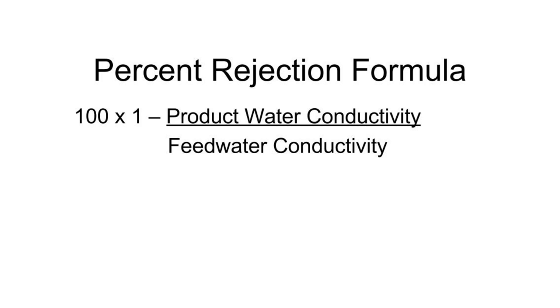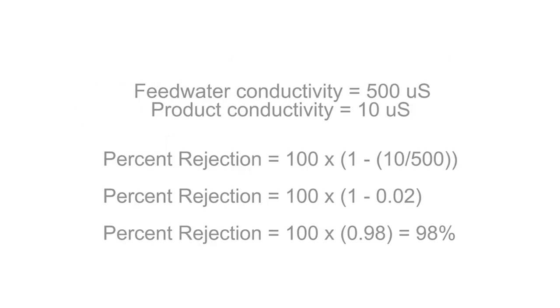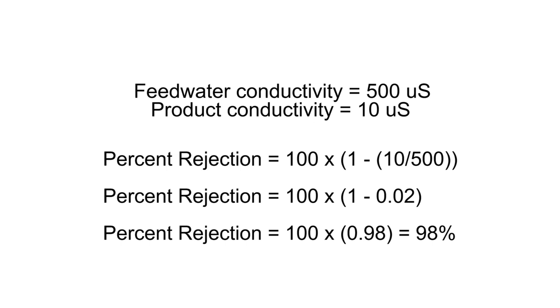If your feed water comes from surface water, such as a river or lake, or from different sources such as two wells, feed water conductivity changes frequently. To account for changes in feed water conductivity, we use a calculation called percent rejection instead of product water conductivity to determine if RO membranes or internal O-rings are damaged. The formula for percent rejection is: percent rejection equals 100 times (1 minus product conductivity divided by feed water conductivity). For example, if feed water conductivity is 500 microsiemens and product conductivity is 10 microsiemens, percent rejection is 98.